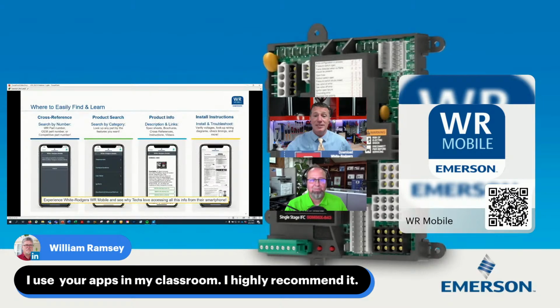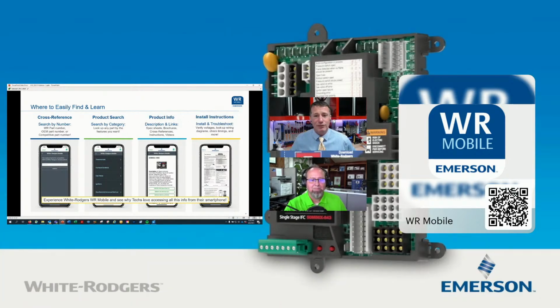Think about the opportunities we have there. If we want to teach flame rectification, it's a difficult thing to teach a newcomer to the industry. It's also difficult to teach someone stuck on reading millivolts that we're not using that, we're not producing voltage. We're measuring current that's being produced in the board, which is high voltage AC coming through our rod and making its way to ground.